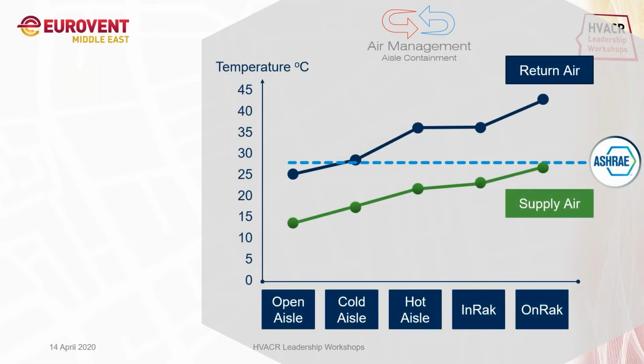I was telling about the temperatures in different aisle containment solutions, which is one is open aisle. We are using a return air temperature of 24-25 degrees Celsius. These are the temperatures to the CRAC unit or the cooling unit. And supply air temperature of 12-13 degrees Celsius, whereas in a cold aisle, we'll be using a much higher 27 degrees Celsius and 15-16 degrees Celsius. In a hot aisle containment, you can see we are even able to use a return air temperature of 36 degrees Celsius and a supply air of 20 degrees Celsius. And in rack, same, we are using a hot aisle system there, 36 return air and 20 supply. And on rack, we are even using 42 degrees Celsius return air and supply air of 27 degrees Celsius.